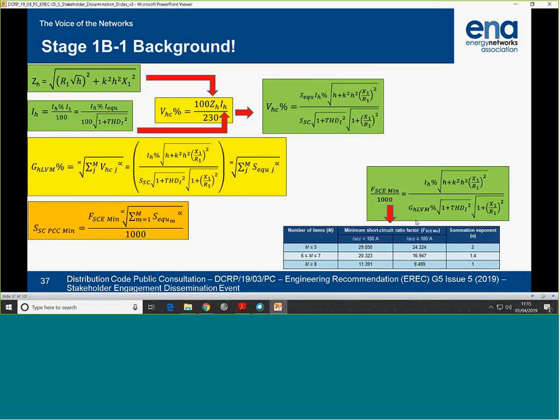I don't want to take too long, but this is the basis. This is in the background document. You can have a look at that at your leisure. The key thing is you've got the harmonic emission limit here. This is to do with skin effect and the X/R ratio. This value here is really what you use for your voltage, how much voltage you're going to allow them to produce. So this is the global harmonic low voltage value, how much you can produce, and it's a modified version of what we derive. The global value is derived from the planning level at low voltage, less the transferred value from high voltage. That's what you're left with to use, and then we've modified it slightly, as is detailed in the background document in one of the answers to that.